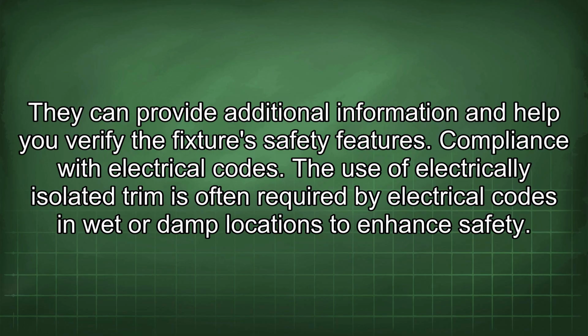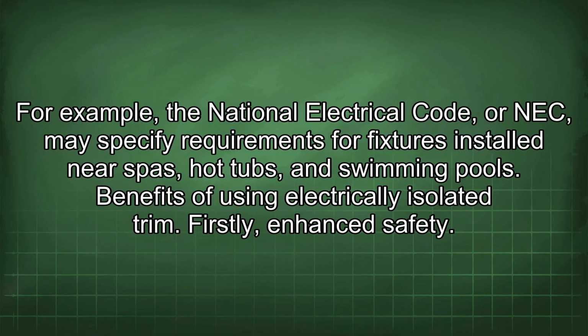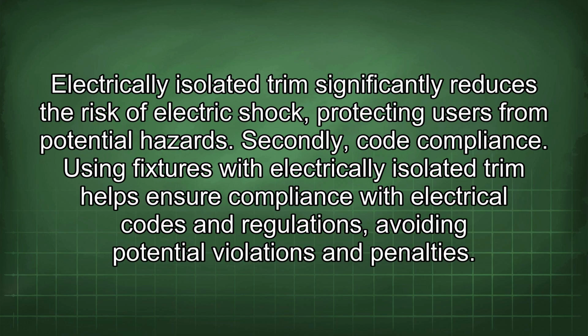Compliance with electrical codes. The use of electrically isolated trim is often required by electrical codes in wet or damp locations to enhance safety. For example, the National Electrical Code, or NEC, may specify requirements for fixtures installed near spas, hot tubs, and swimming pools. Benefits of using electrically isolated trim. Firstly, enhanced safety. Electrically isolated trim significantly reduces the risk of electric shock, protecting users from potential hazards.